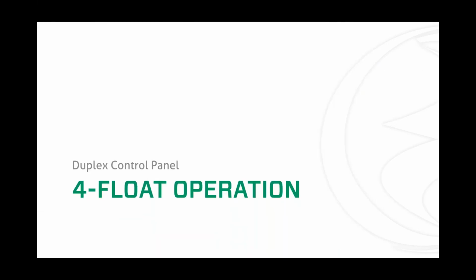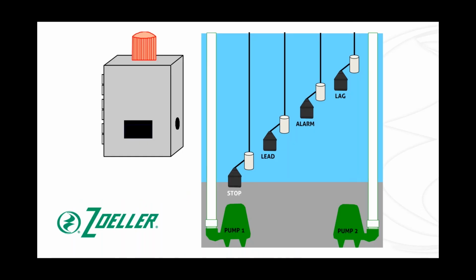So now all of Zoeller's duplex control panels can be wired up to accept 4 float switches. Sometimes people think that a 4-float setup is better and preferred over a 3-float setup. Sometimes it is, and sometimes it isn't. But let's just go through a 4-float operation and talk about this. So, as you notice here, we have a duplex pump setup, and we have it wired up with 4 weighted float switches in this particular application.